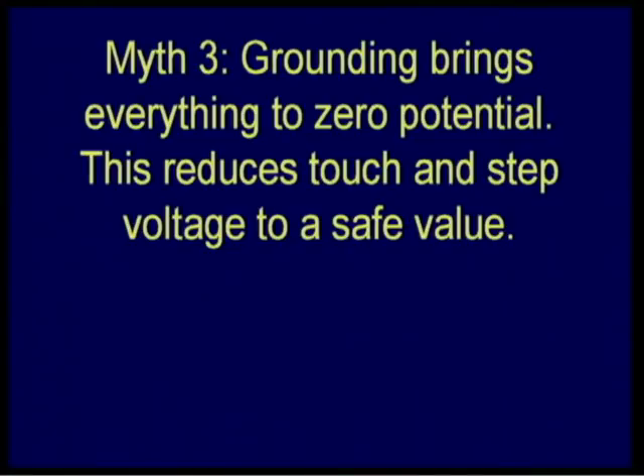Do they still drive ground rods? Yeah. Why? Because we've been driving ground rods at poles. It didn't work before, but it doesn't matter. We drive ground rods. No, ground rods serve no purpose. What serves a purpose is what? An equipment grounding conductor. So anybody making a statement that grounding makes it safe, that electrons are trying to go to ground, is false.